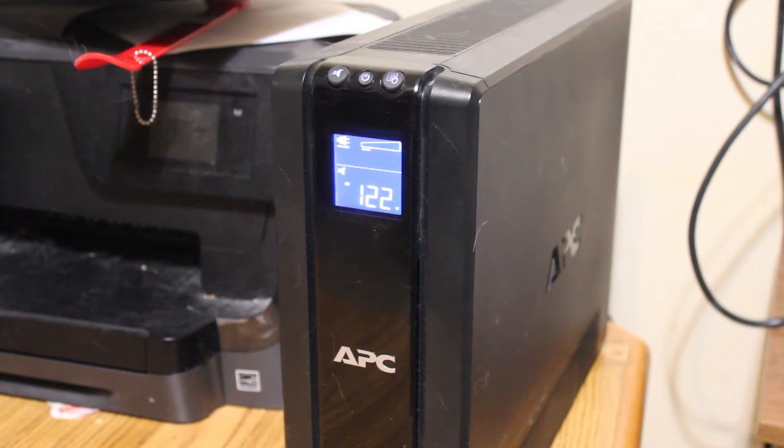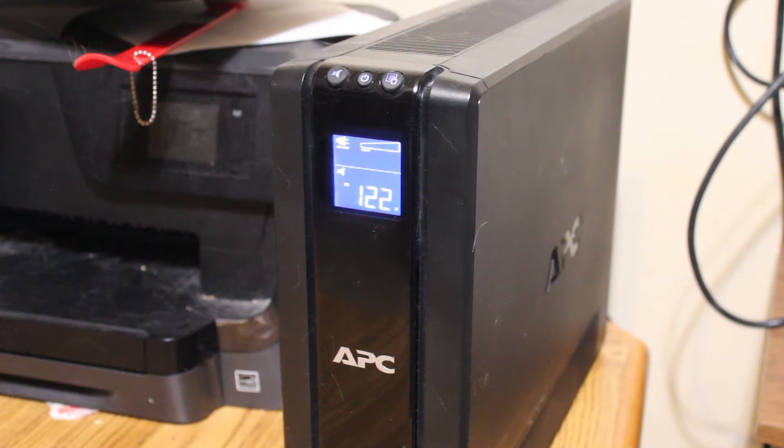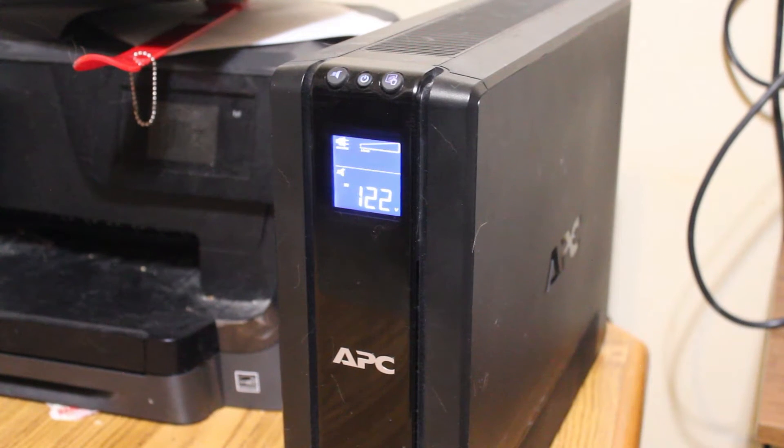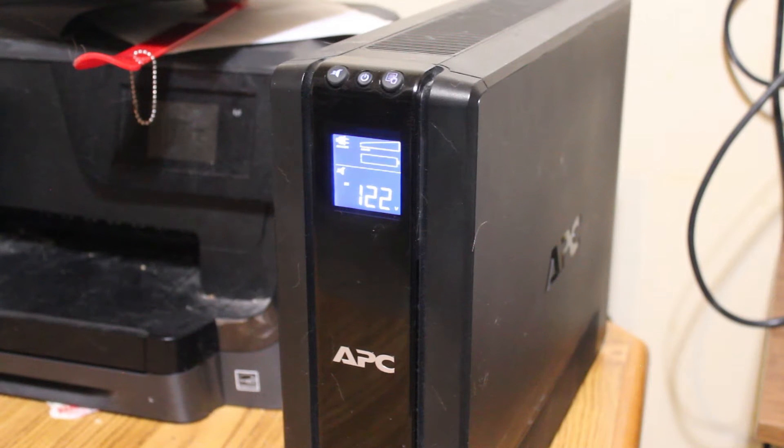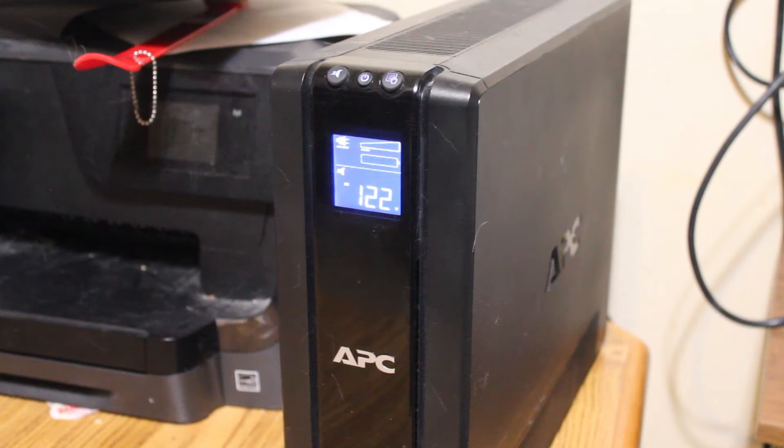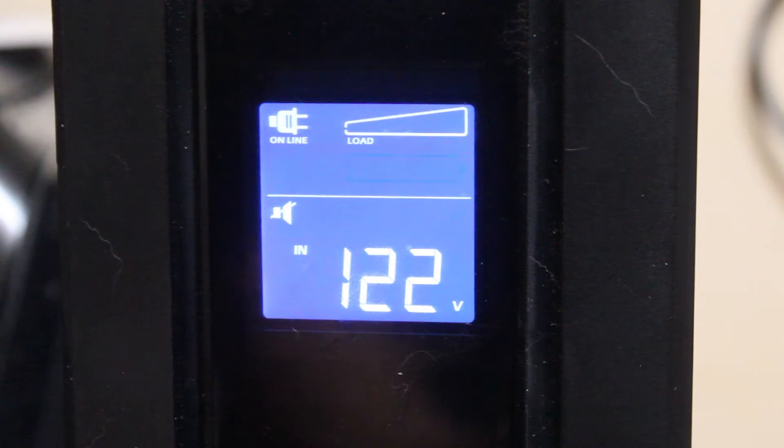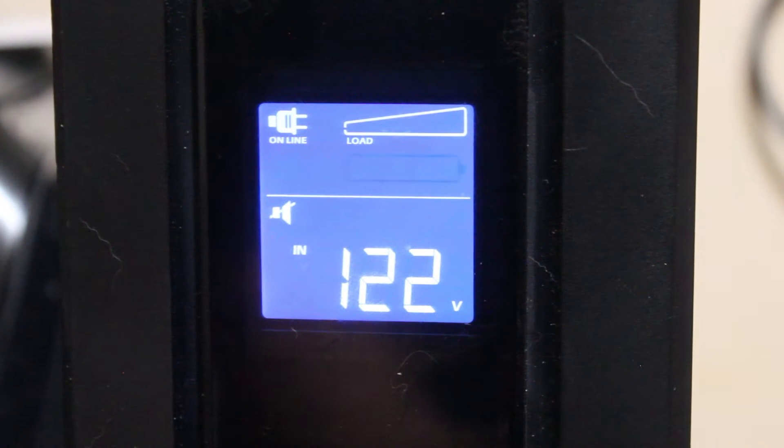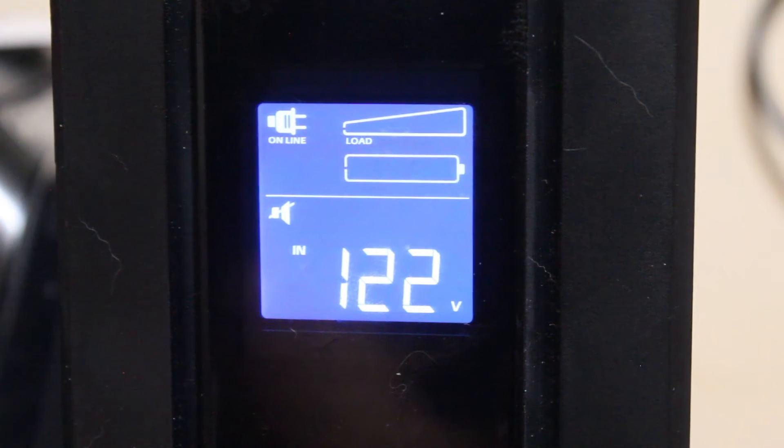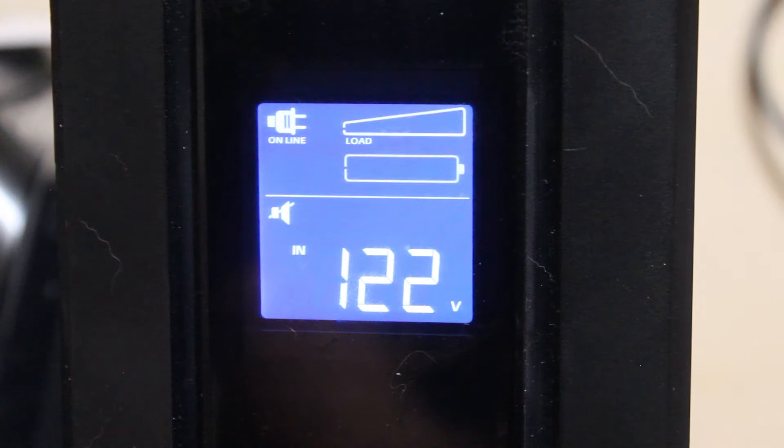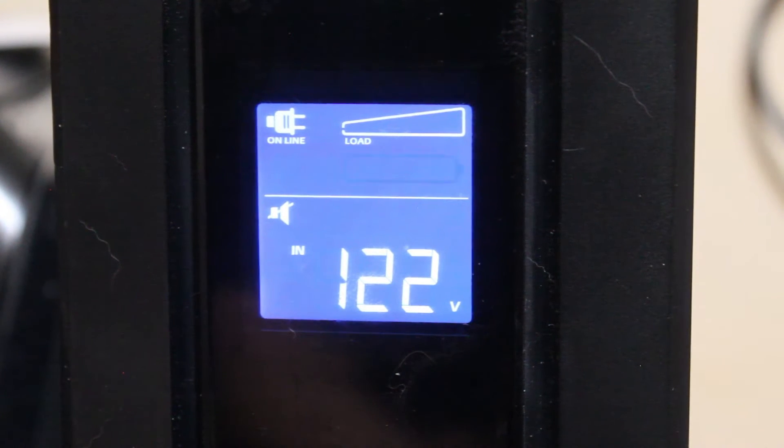So once you've determined that the batteries do need replacing, and the flashing battery light there is definitely that indication, this UPS has been plugged in for about four years. I did bench test the unit and it was doing just fine, other than needing new batteries. From the display, we can tell that the charger isn't even charging the battery anymore.